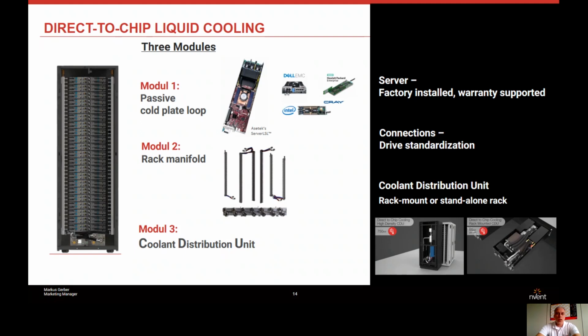And the last component you need is the so-called CDU, coolant distribution unit. Inside this coolant distribution unit, you have a pump or redundant pumps that pump the liquid through the manifold, through the server, and let it circulate, taking away the heat, to a liquid-to-liquid heat exchanger that is integrated in the CDU, where you then transfer the heat from the server to the facility pipework. These CDUs, as of today, can be a rack mount 19-inch CDU in the bottom of a rack, or you say, no, I have a system of 2, 3, or 4, or even more racks that I want to support with one unit. Then you can use a standalone CDU just beside the rack, supporting the infrastructure.